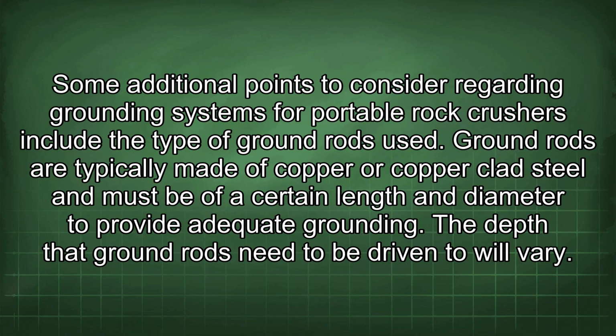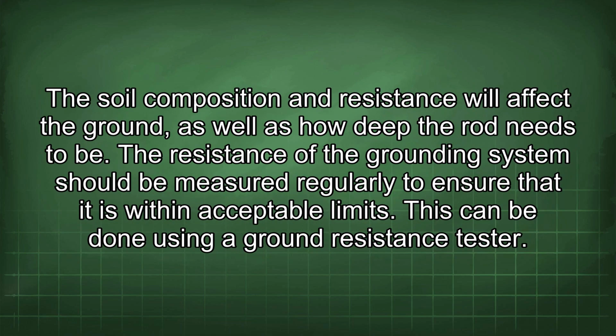Some additional points to consider regarding grounding systems for portable rock crushers include the type of ground rods used. Ground rods are typically made of copper or copper-clad steel and must be of a certain length and diameter to provide adequate grounding. The depth that ground rods need to be driven to will vary. The soil composition and resistance will affect the ground, as well as how deep the rod needs to be. The resistance of the grounding system should be measured regularly to ensure that it is within acceptable limits. This can be done using a ground resistance tester.